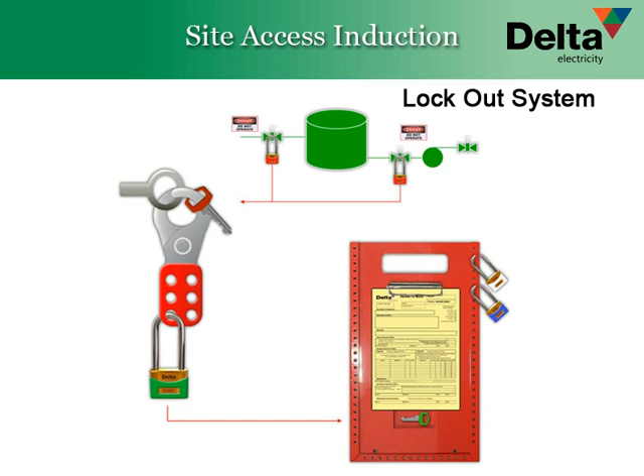When plant is isolated to give people access, an appropriate isolation to effectively control the risks associated with all sources of energy is determined and documented. This is checked to ensure the correct isolation has been prepared and verified to ensure the locks and tags are on the correct isolation points.